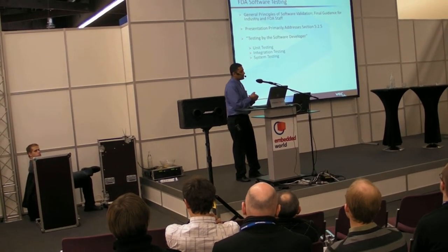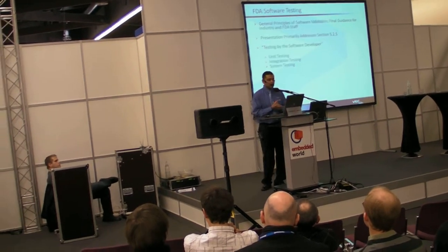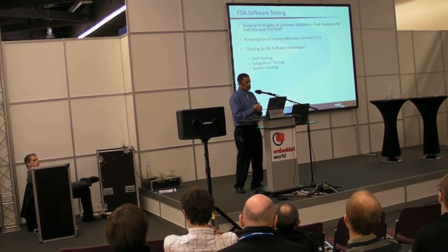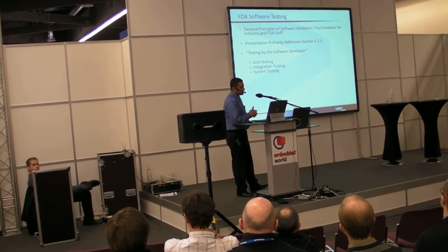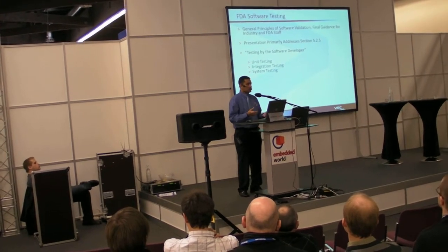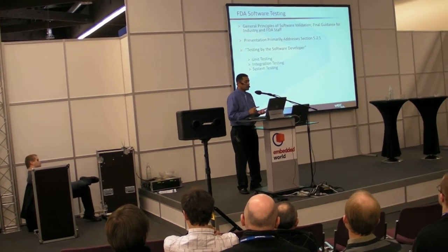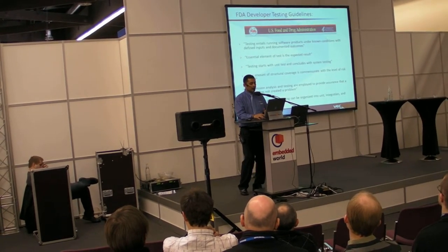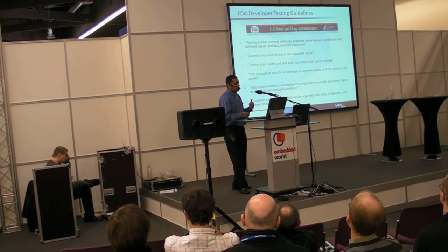FDA testing. So, FDA testing is for medical devices, and there's a guidance in there. In general, it talks about section 5.2.5. It talks about testing by the software developer, and there it explicitly calls out the need to do unit testing, integration testing, and system testing. So, three key phases of validating the software. And it goes into a bit more detail.